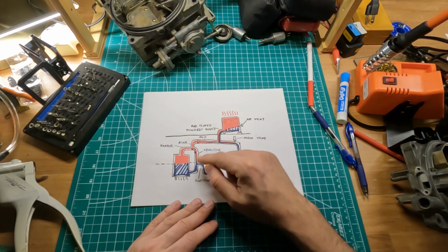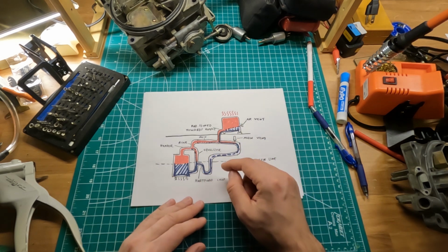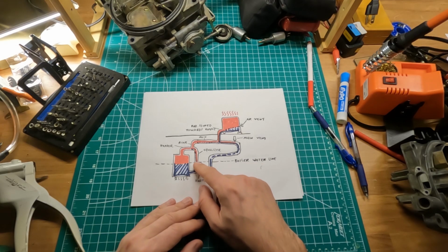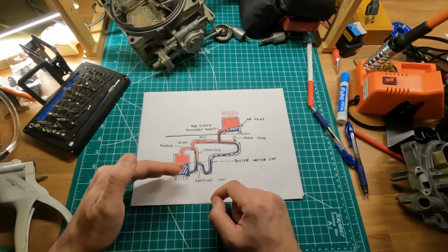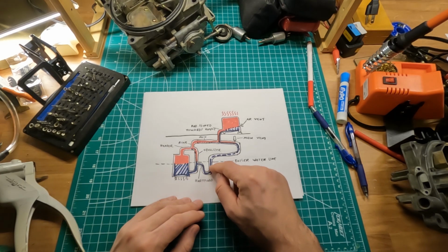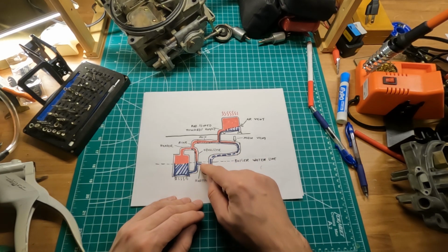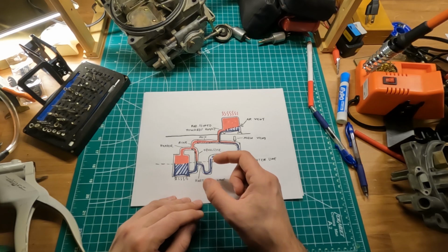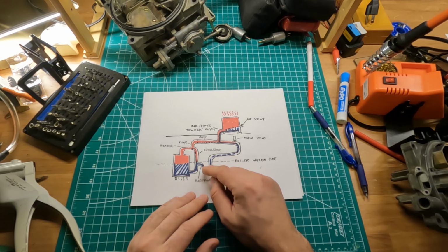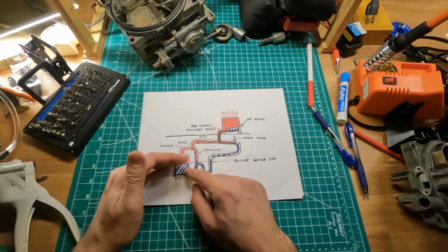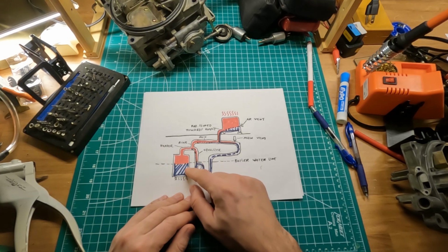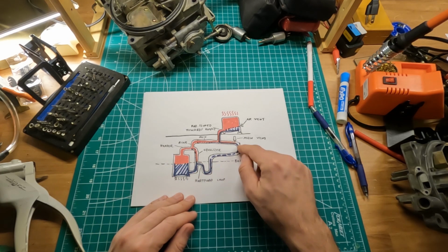And then we have something called the Hartford Loop, which was basically a preventive measure, so that if there was a leak in the system somewhere, the water doesn't flow out of it. The Hartford Loop is usually a short pipe that's very close to the boiler, so that the boiler never loses water via some kind of leak along the path.